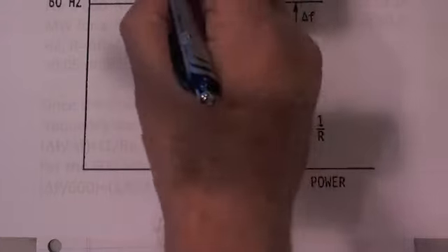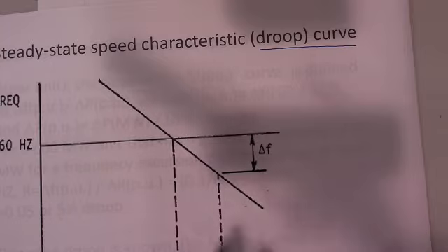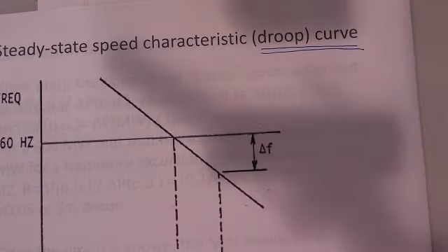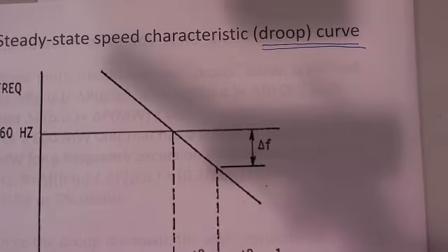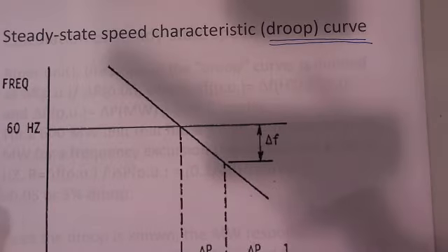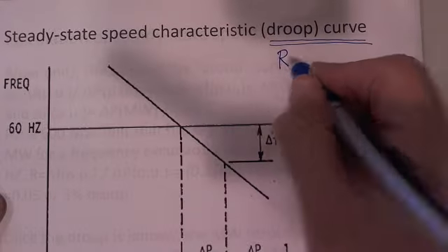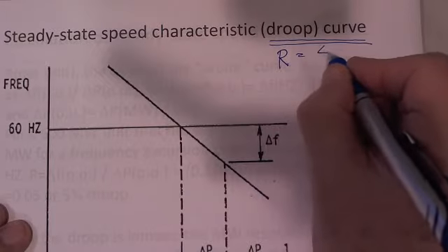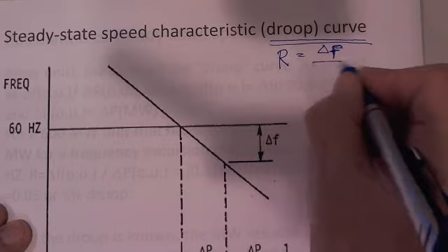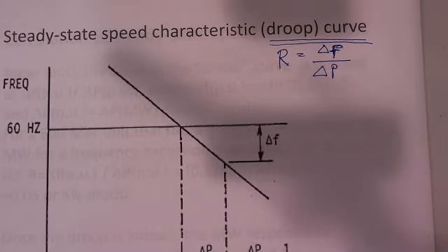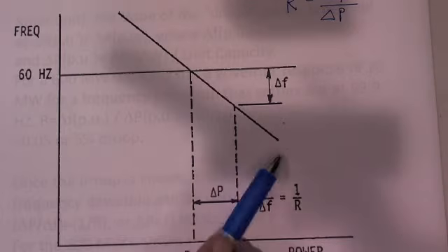So there's a characteristic to the governor called, you can call it the speed characteristic. That's a nice word. The nomenclature that got used is the term droop. Call it slant, whatever you will. It just means the fact that the characteristic runs like this, and it simply says that the characteristic, the droop is called R, okay, and R is equal to the change in frequency, let's use a small f, the change in frequency to the change in power. It's usually expressed as 1 over R is delta P over delta F. So it's the ratio of frequency change to power change on that governor. So that's the speed characteristic right there, is that slope.